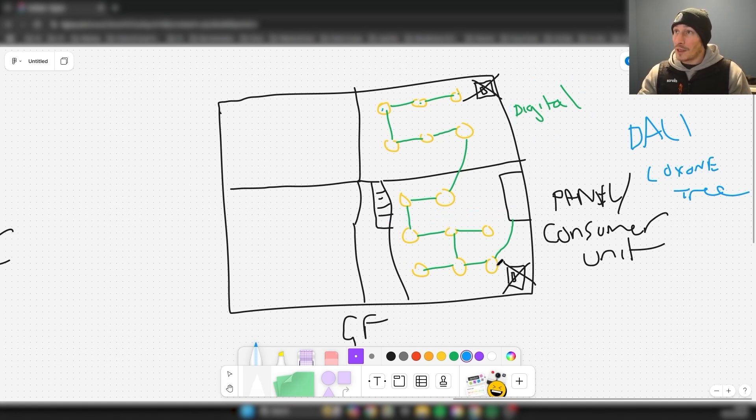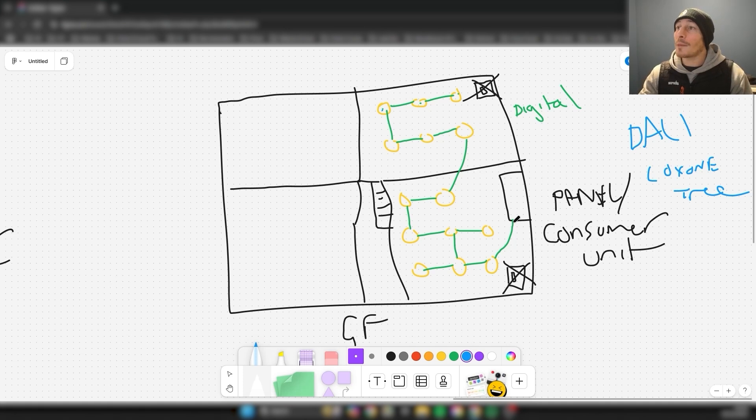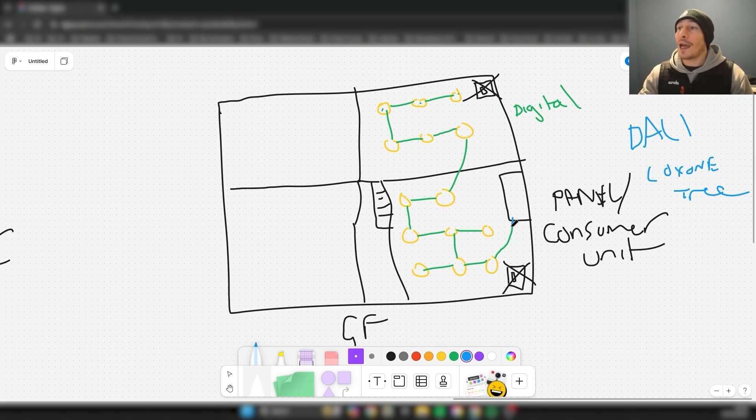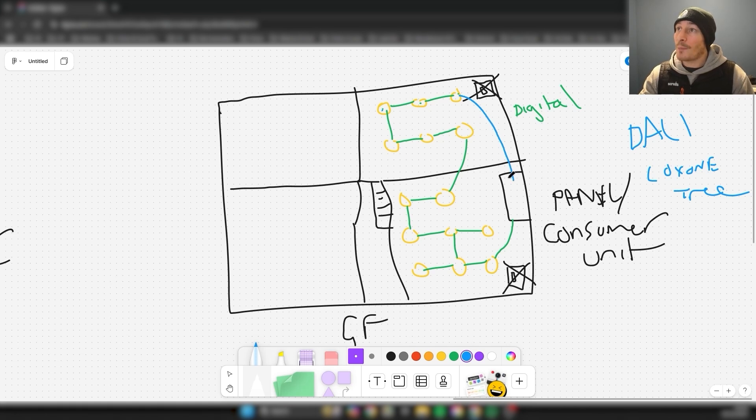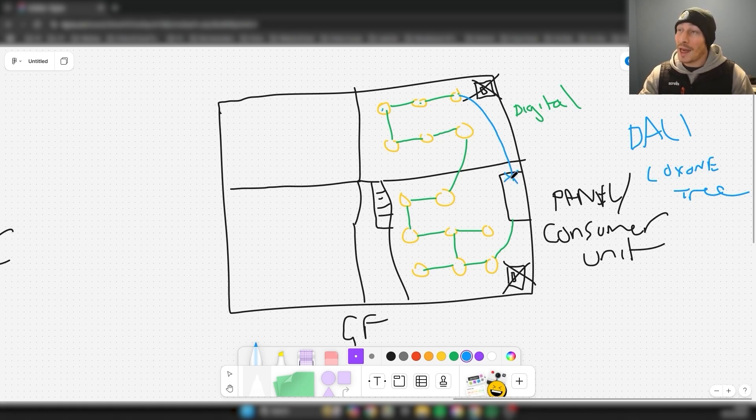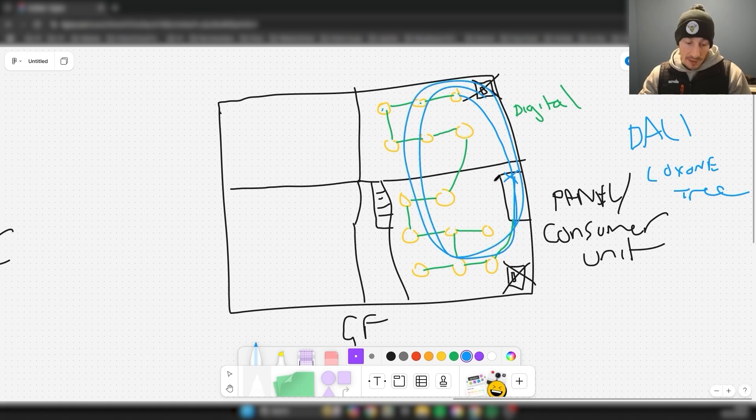What I would do, just a little bonus tip, is let's say that you are wiring it in a similar way to what you're doing here. We're coming out of the panel this end and then we're covering all of this. I would still encourage people to wire this leg back to the panel, but not connect it. Don't connect it because then we create that ring which I mentioned isn't good.